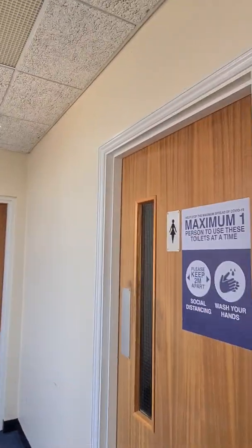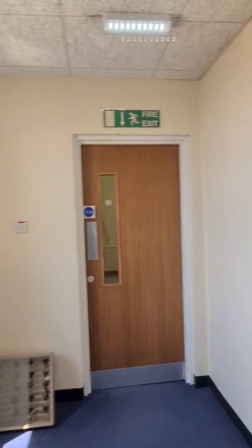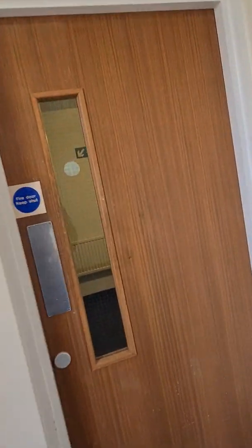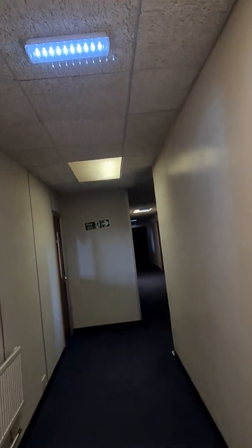So basically just keep walking the testing route the way I'm showing you. I'll map everything out for you on a schedule so you can understand in writing what I've done. But the idea of this visual training is it allows you to simply follow me and test the emergency lights. Right, this one here in the corridor tests basically all the emergency lights in this fire compartment here. Okay, so you've got 1, 2, 3 emergency lights in this fire compartment. And there's a next one here, and this tests all the emergency lights in this fire compartment, and I think you've got 3 emergency lights here.